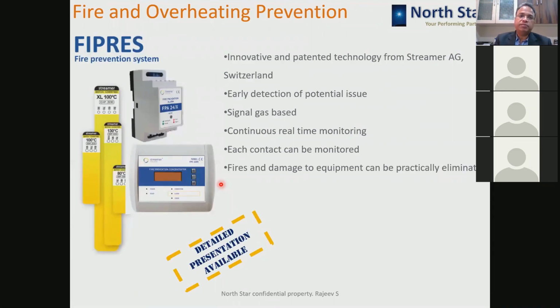Okay, then we have a fire and overheating prevention system for control panels, where we have this unique signal gas based technology. These are self adhesive labels which can be put on electrical contacts, live contacts, and at an activation temperature, say 100 degrees centigrade, if the joint is poor, the temperature will increase slowly from 25-30 degrees centigrade to higher values, and it will reach activation temperature. At that temperature, this label will get operated, and it will release a non-hazardous gas, safe to humans. That gas is captured by this fire prevention alarm system, and the alarm is given to this fire prevention concentrator, and from there this signal is used for your own safety network, fire equipment operating network, or just indication purpose. So you can use the information for safe operating of your devices as per your own comfort and convenience.